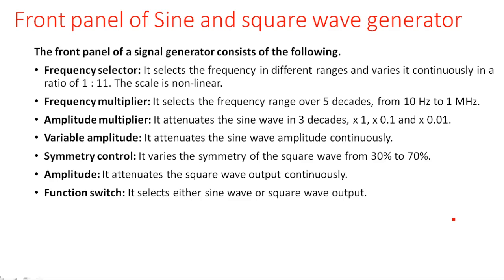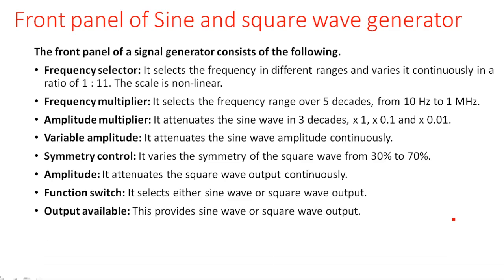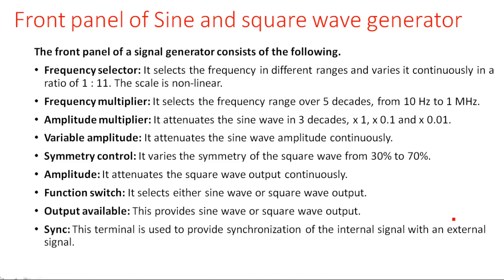The function switch selects either sine wave or square wave output. The variable output provides the sine wave or square wave signal. The sync terminal is used to synchronize the internal signal with an external signal — when connecting an external supply, the external signal can be synchronized with the internal signal. Another front panel control is the main on/off power switch.